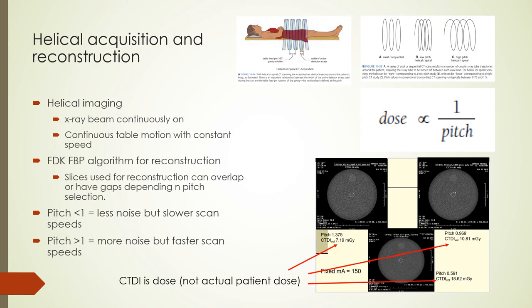Helical imaging is a continuous acquisition mode where the beam is continuously on as it rotates and the table moves at constant speed. Images are reconstructed using the FDK filtered back projection algorithm. For pitch less than one, slices used for reconstruction overlap, leading to less noise. For pitch greater than one, there are gaps between slices, leading to a noisier image. Pitch less than one results in slower scans and higher dose, while pitch greater than one results in faster scans and lower dose.